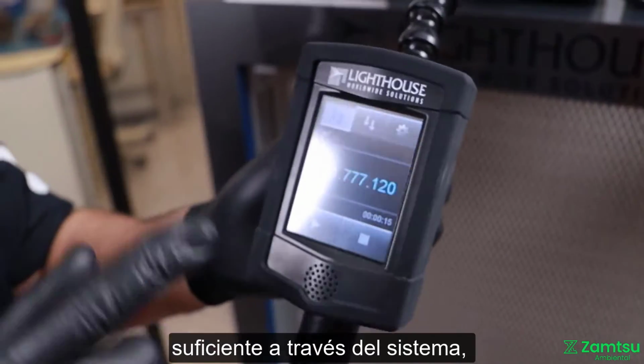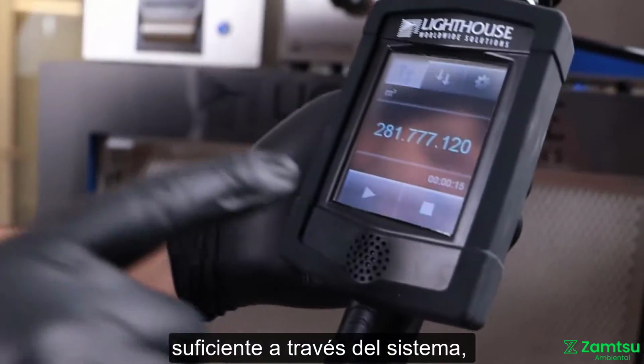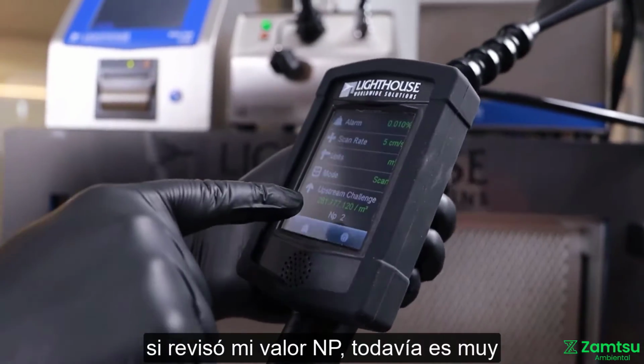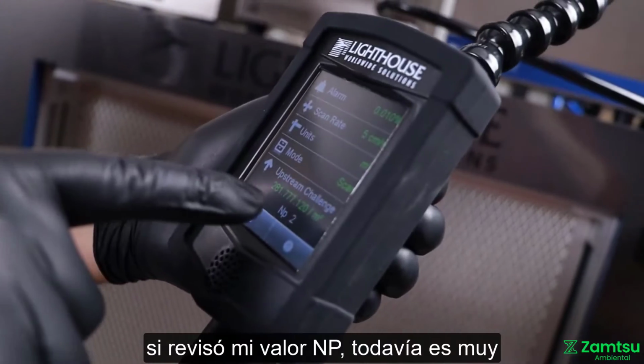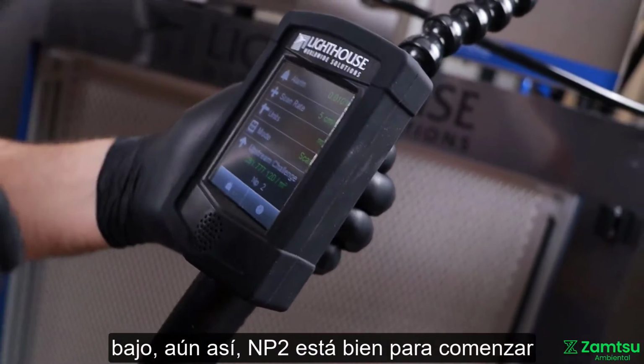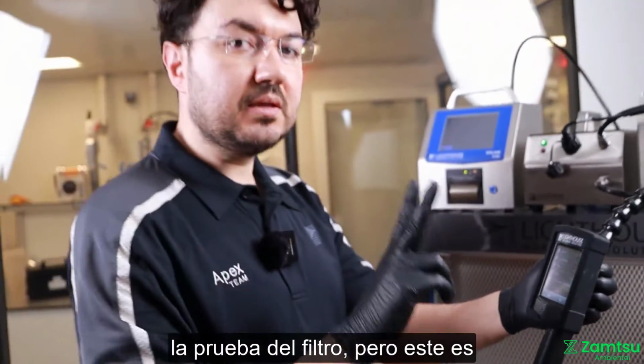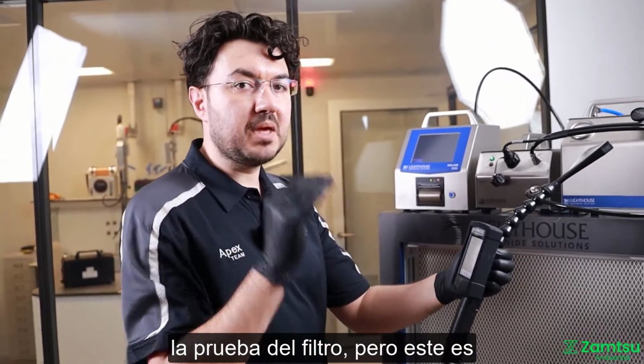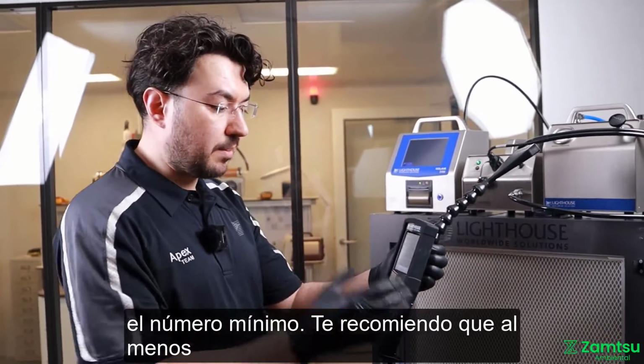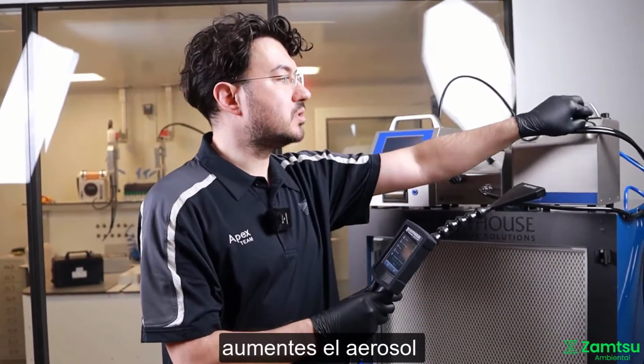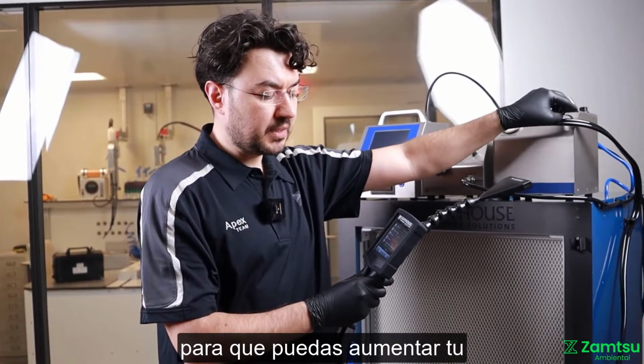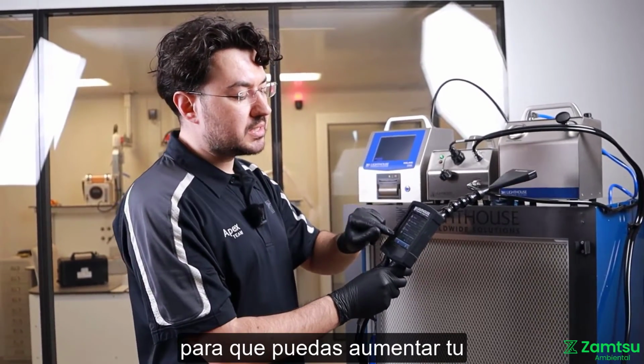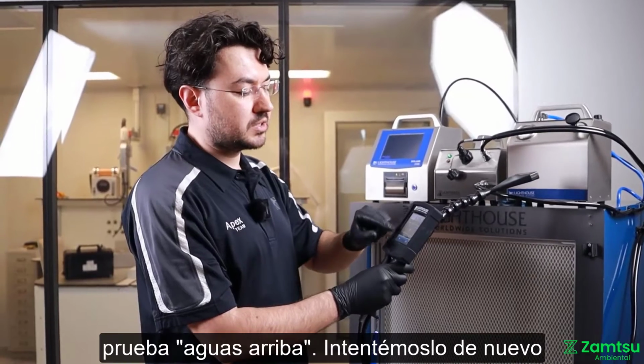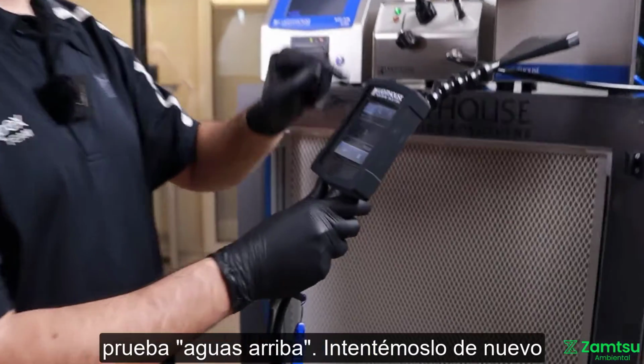Now, we have both homogeneous and sufficient aerosol through the system. If I check my NP value, it's still very low. Still, NP2 is okay for starting filter testing, but this is the minimum number. I recommend you to at least increase your aerosol a little bit more so that you can increase your upstream challenge. Let's try it again.